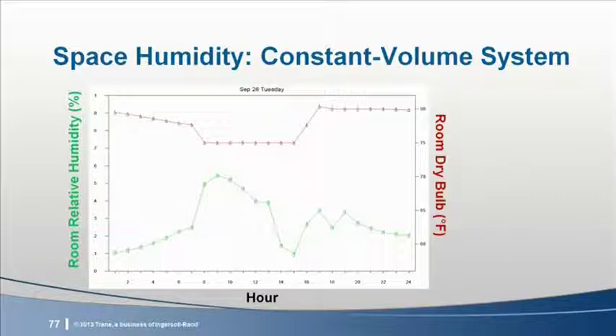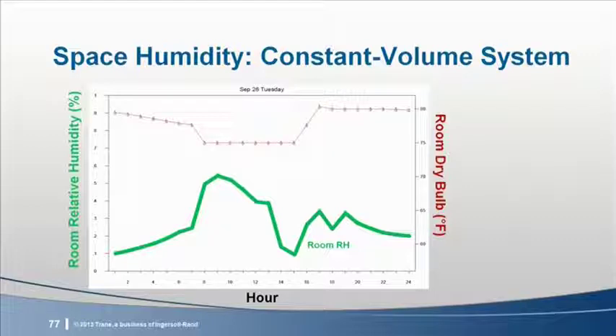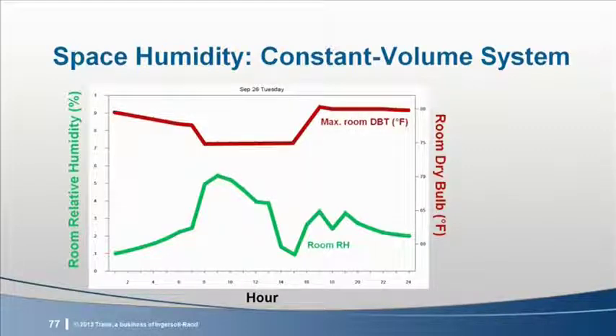The green line near the bottom of the chart featuring open boxes is the space relative humidity for the modeled classroom from the constant volume single-zone alternative in September. Maximum space dry bulb temperature is represented as the red line featuring open triangles. After the students arrive at hour 7, the space relative humidity peaks and fluctuates throughout the occupied period. Space temperature falls from the unoccupied set point to the occupied set point, 75 degrees Fahrenheit, once occupancy begins. Next, let's look at the same chart for a single-zone VAV system.